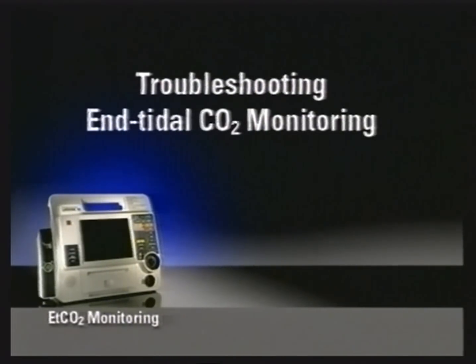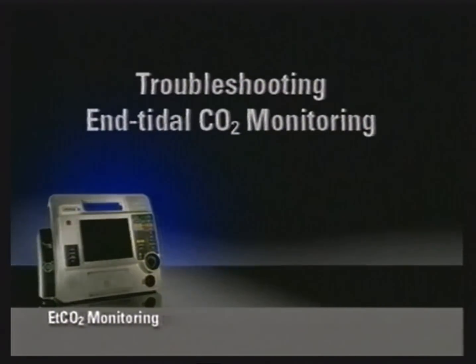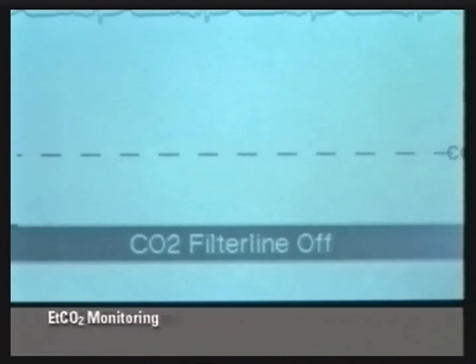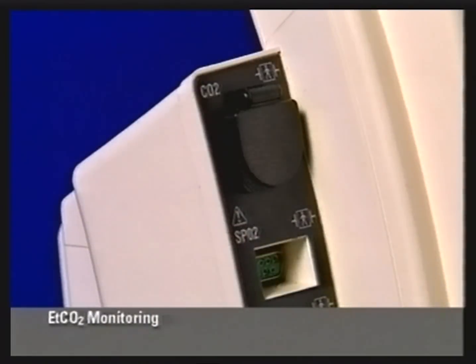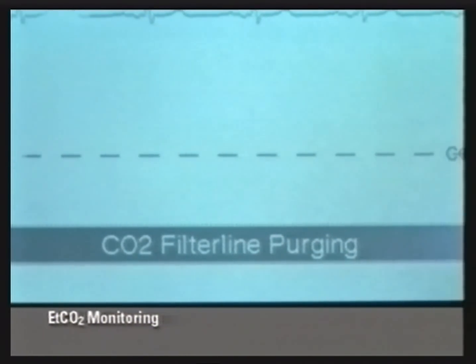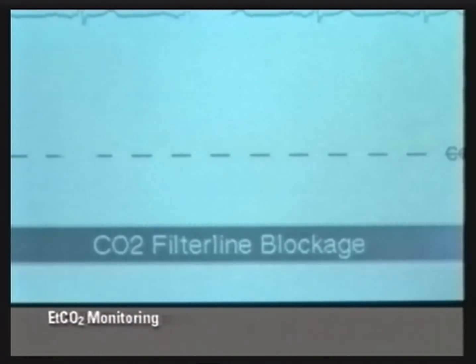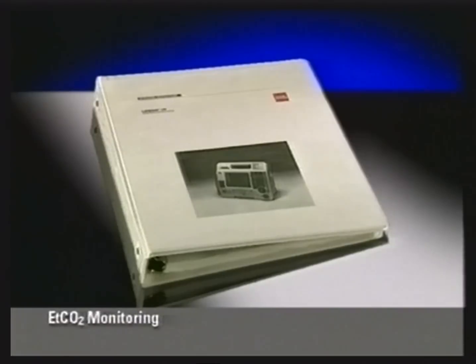The Lifepak 12 end-tidal CO2 monitor has built-in messages to help troubleshoot problems that may arise. CO2 filter line off indicates that the filter line is disconnected from the CO2 connection on the monitor. Reconnect the filter line to the monitor as previously described. CO2 filter line purging indicates the filter line may be clogged or twisted, or in the case of air transport, that a rapid altitude change occurred. After 30 seconds of unsuccessful purging, the message CO2 filter line blockage appears. Remove and reconnect the filter line, or replace if necessary. For more information about troubleshooting, messages, and suggested corrective actions, consult your operating instruction manual.